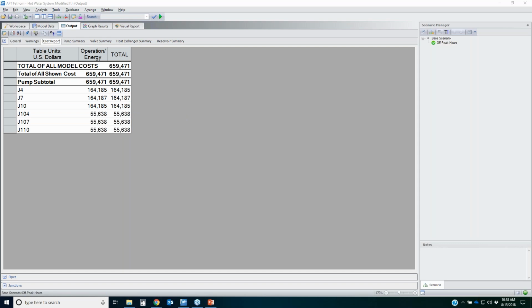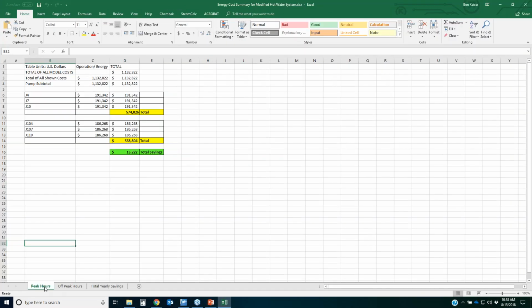Well, what are the total cost ramifications on that? I've got a spreadsheet for that I'm going to open up here real quick and just show you the total costs overall. As that's opening, I'll go ahead and drag it over. So here's my peak hours. As you can see, for my peak hour operation using control valves, it's $574,000 a year. With a variable speed drive, you get $558,000. So that is $15,000 a year of savings. And again, this is a dinky little system. It's not real. Imagine if you did this for your own system that was real.